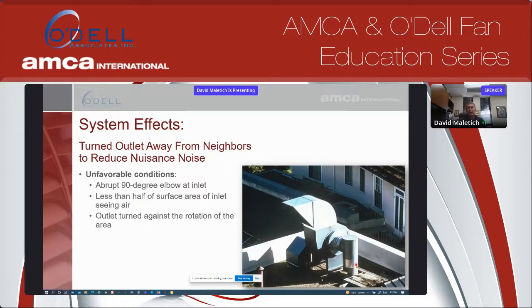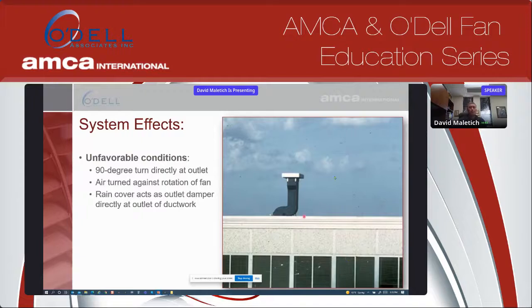Inlet side, we have this abrupt 90-degree elbow. It creates a lot of turbulent flow as air enters the fan. This is the actual size of the inlet. They had to put this orifice plate here on the fan to gooseneck it down from this size down to the ductwork size. So when this fan was tested in the field, it was only performing about 60% of its catalog rated flow. I have no idea. This is on top of a federal building.